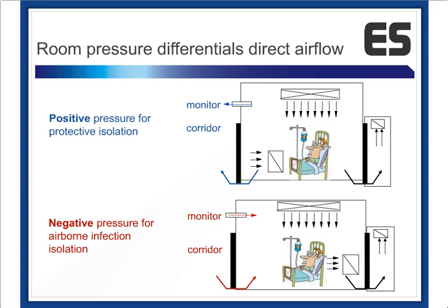Just opposite that, we would see a negative pressure room for airborne isolation. So there's our rooms where there's a patient, and let's say we've got a patient that has active tuberculosis, and we want to protect everyone around them from the potential of acquiring that. So in that case, we're going to remove more air from that room than we're going to supply. And the relative pressure of that room to its adjacent spaces is going to be negative. Air will flow underneath the door from the corridor and into that room, and we will not typically see contaminants go outside of it. Both of these types of rooms would have pressure monitors and alarm systems on them.